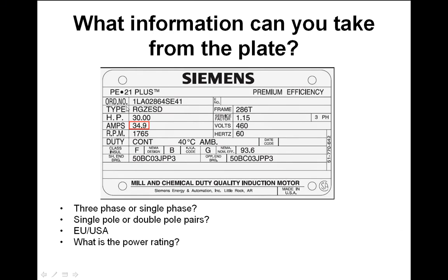Let me take you through these plates. This is a typical plate you'll find on every three-phase motor. You get the manufacturer name and crucial information — it says three-phase here. The voltage also gives an indication: if it's 460 or 415 rather than 230 or 110, that's a three-phase motor. This one is made for the USA — 60 Hz supply. Quick question: would it work on 50 Hz?